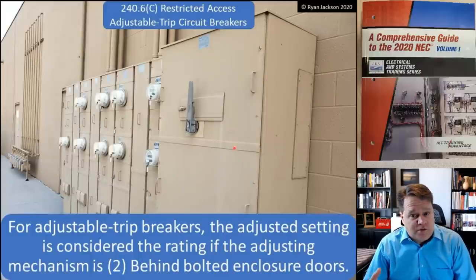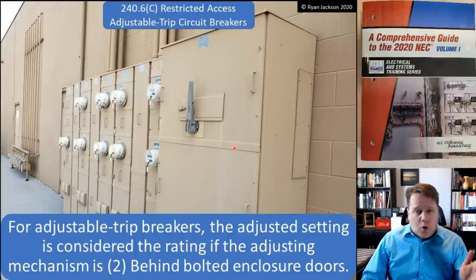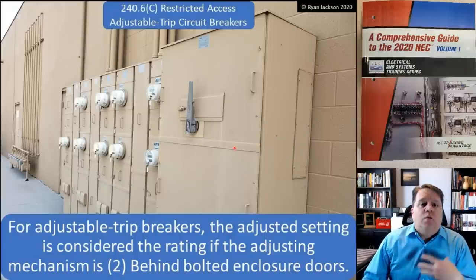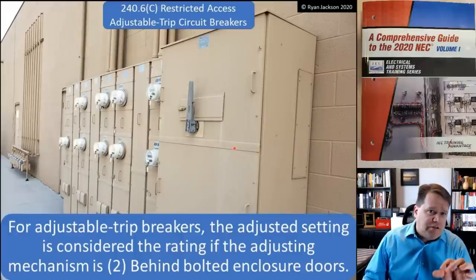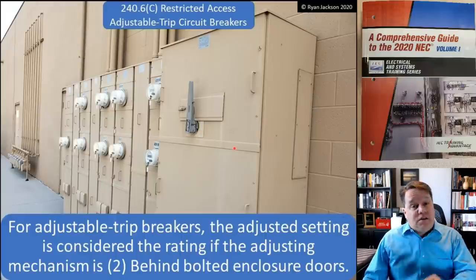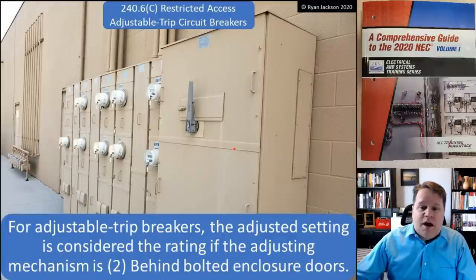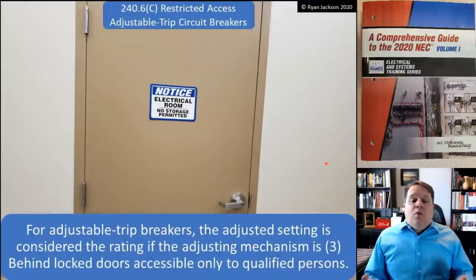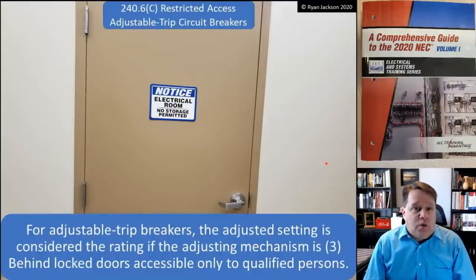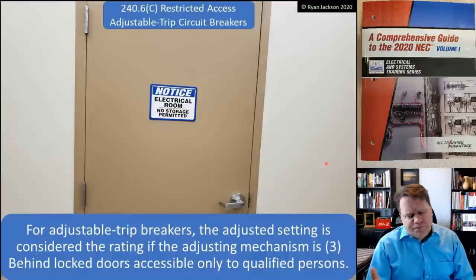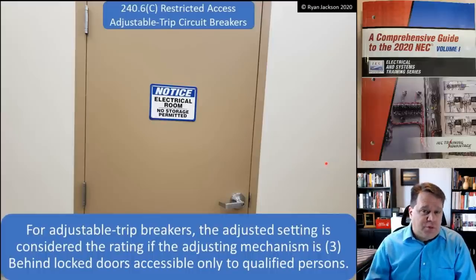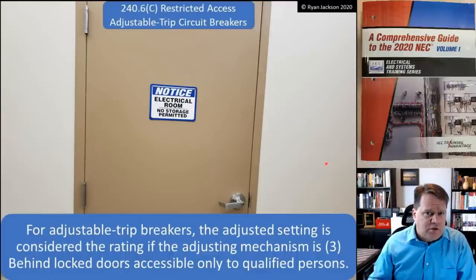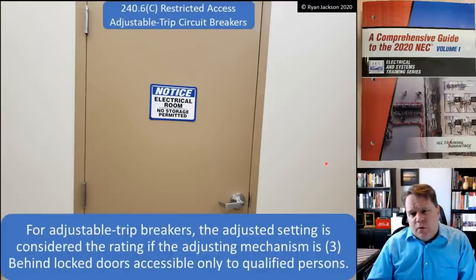Item two is if the adjustment mechanisms are behind enclosure doors — and you only need any one of these to be true to achieve restricted access. Usually when you buy an adjustable trip breaker it's behind a sealed cover, so you've already complied. Item three is having the equipment behind locked doors accessible only to qualified persons. Normally we meet all of the allowances, and you only need to have one of them.